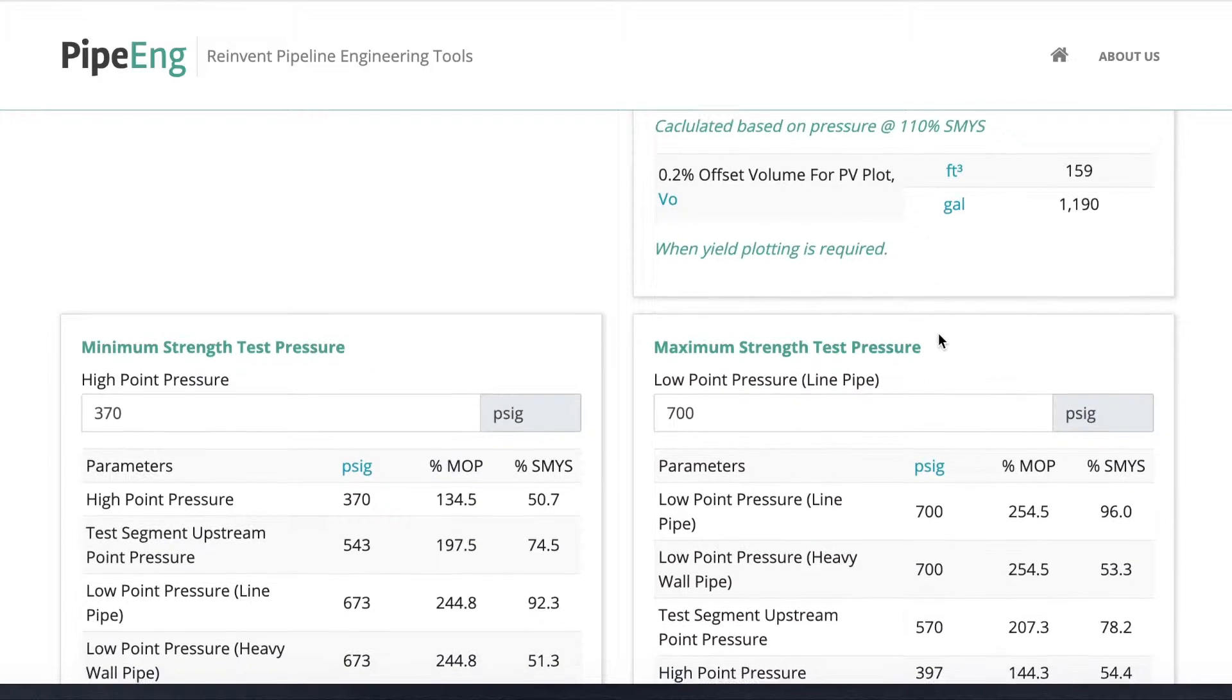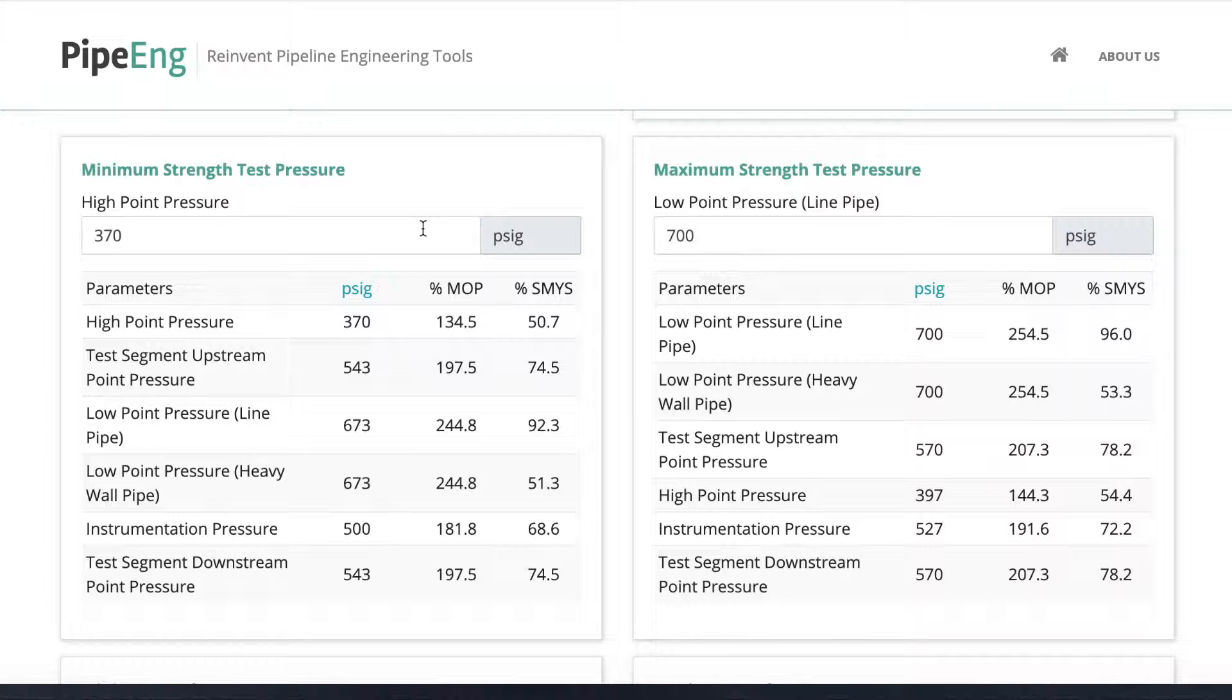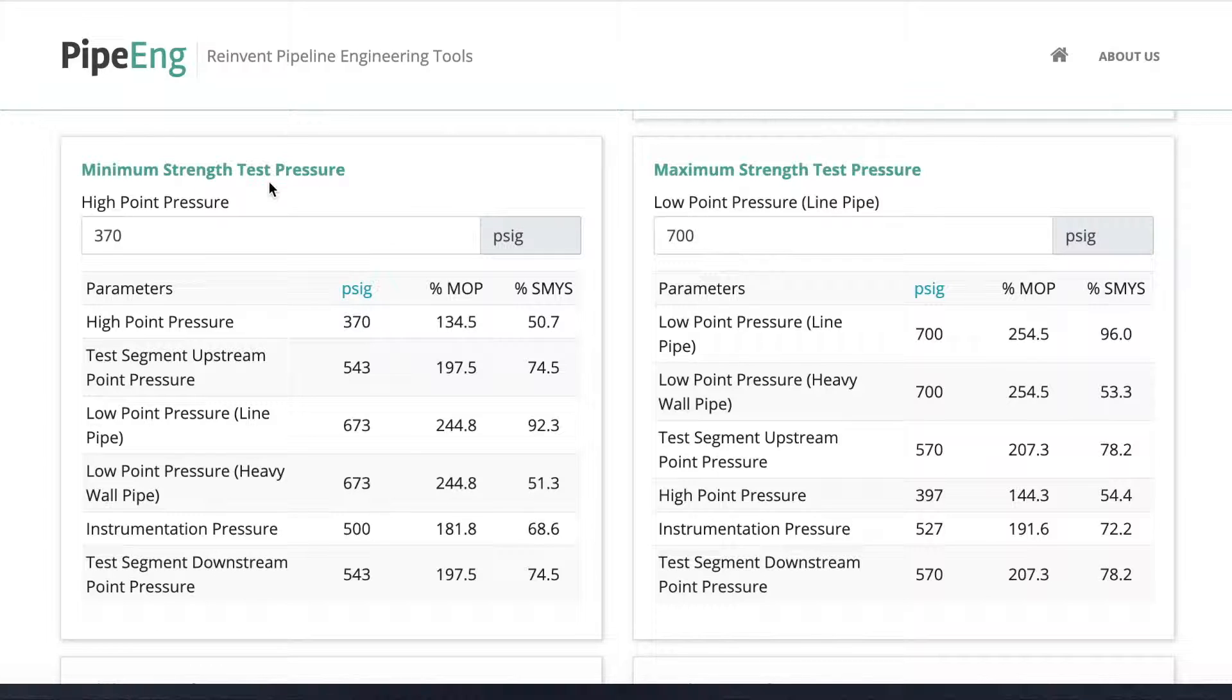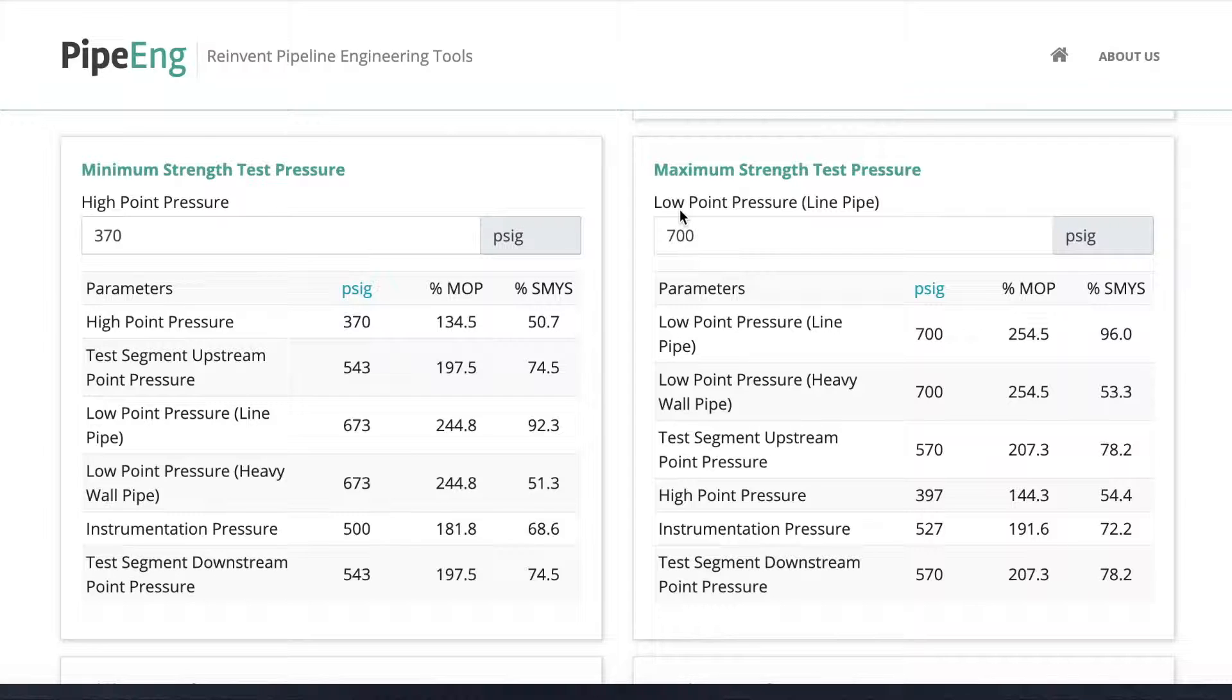So now, the next section is to help us to determine what test pressure we should use. As you can see, we have a minimal stress test pressure scenario, and also have a maximal stress test pressure scenario. The minimal test pressure we will see for our pipeline system is going to be at the high point. And similarly, the maximal test pressure we will see will be at the low point of the pipeline system, because that's where we will see the maximal static head. So usually we will run both cases to determine a reasonable range that can help us to set the test pressure.